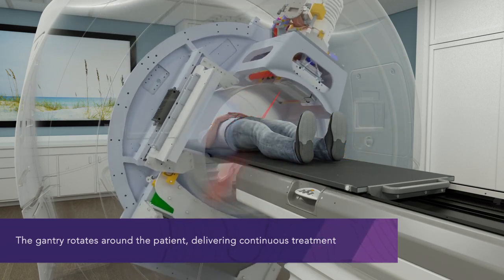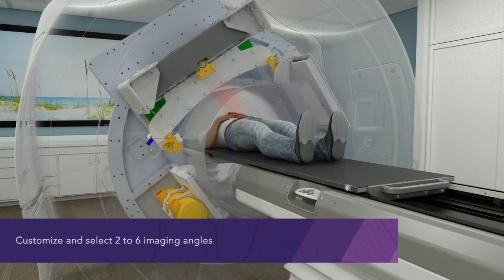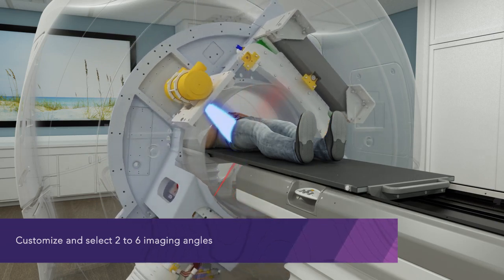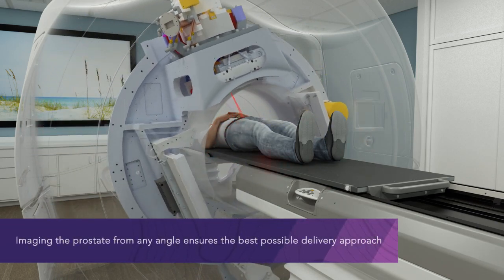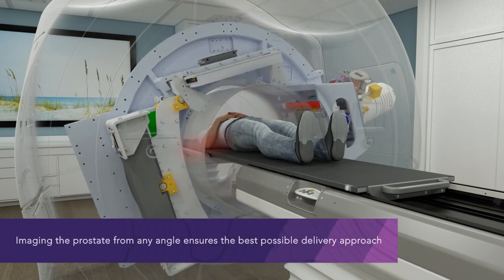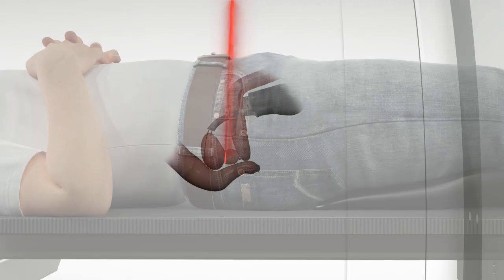The system automatically assists clinicians in the selection and customization of two to six KV imaging angles per gantry rotation, based on the imaging frequency and viewing angles required to detect the prostate's movement. The ability to image at any angle and interactively adjust the position and number of angles as treatment is delivered ensures the best possible unobstructed views of the prostate, while adding no additional time to treatment setup or delivery.